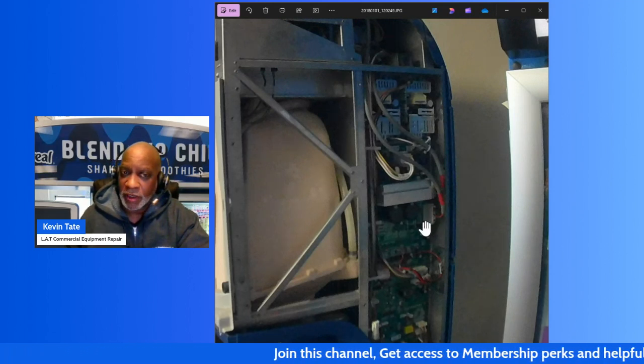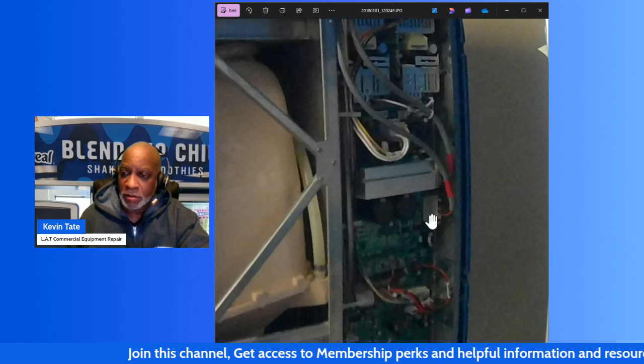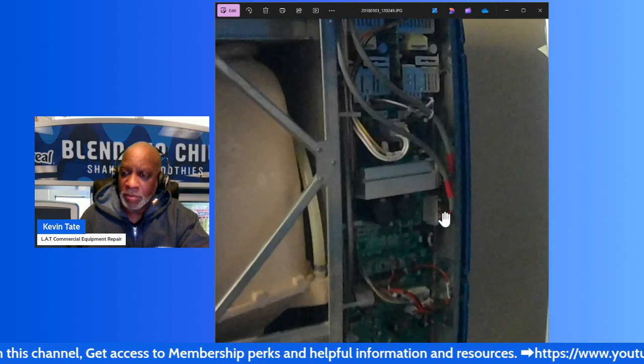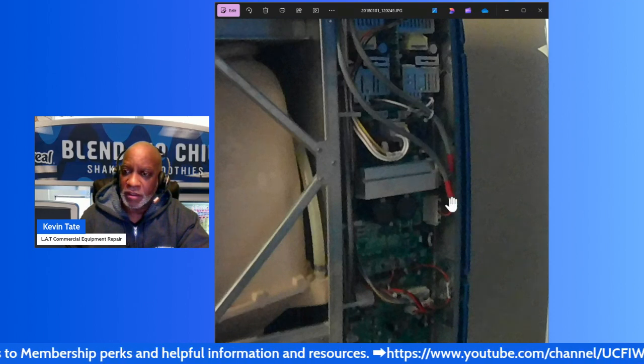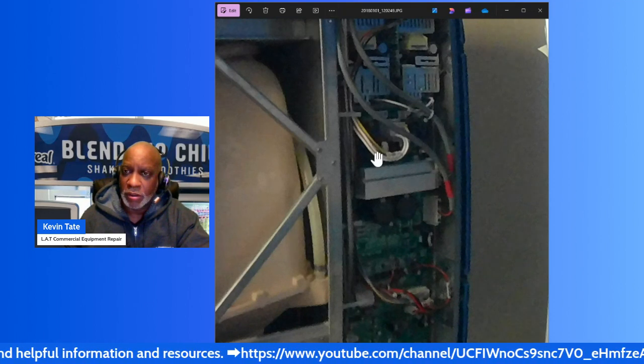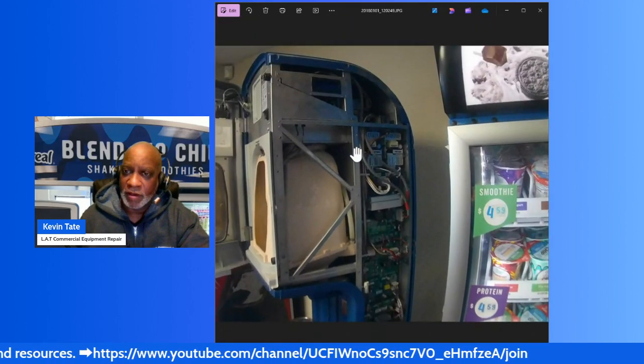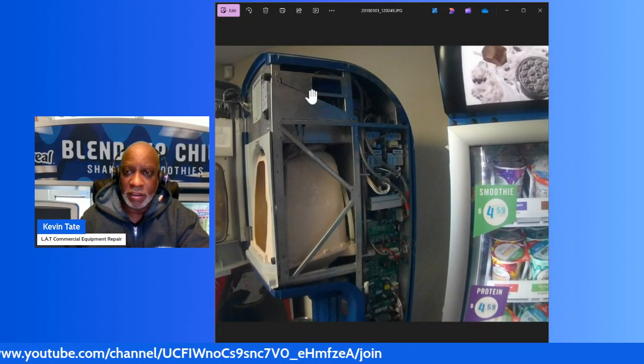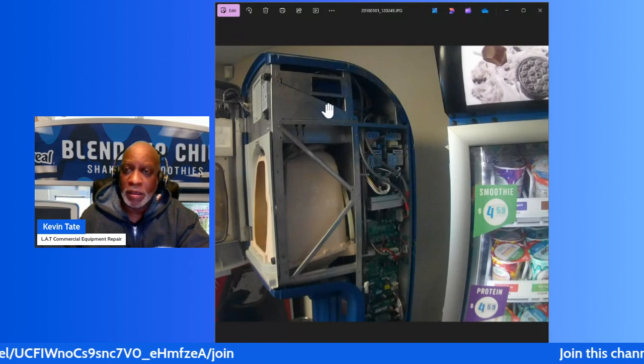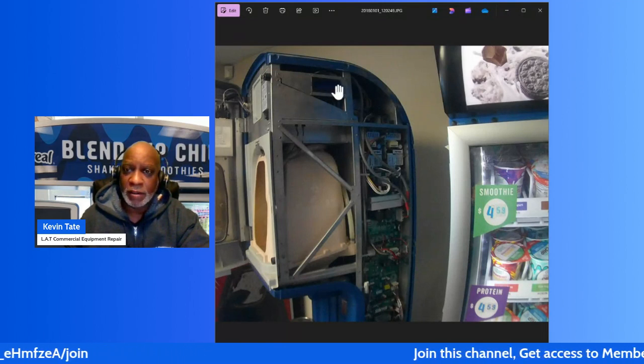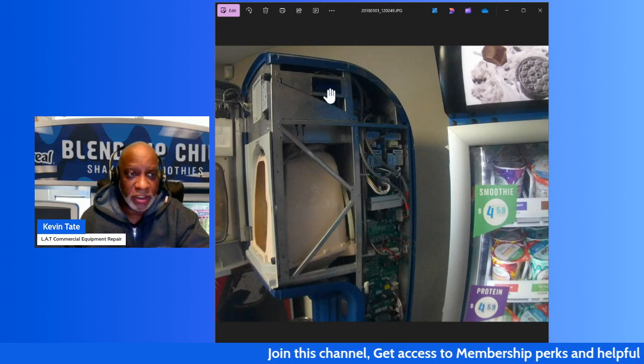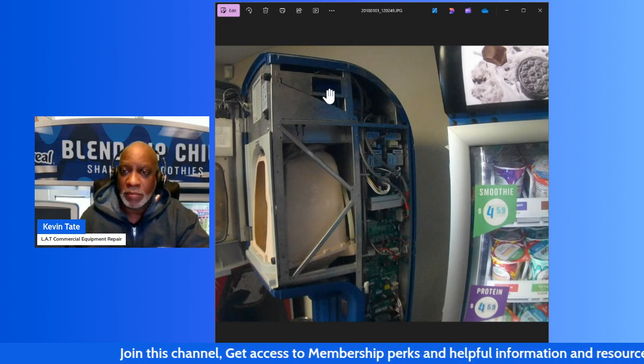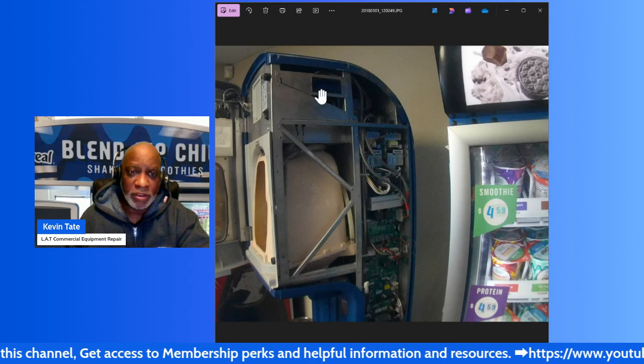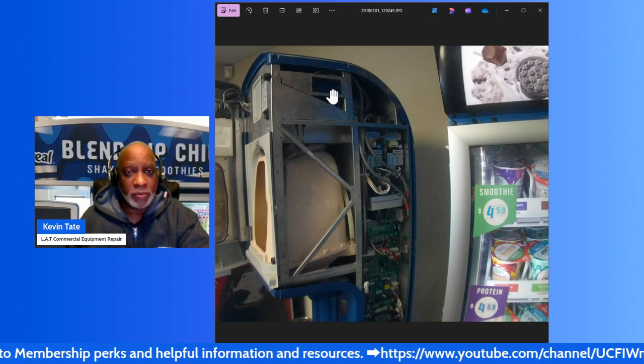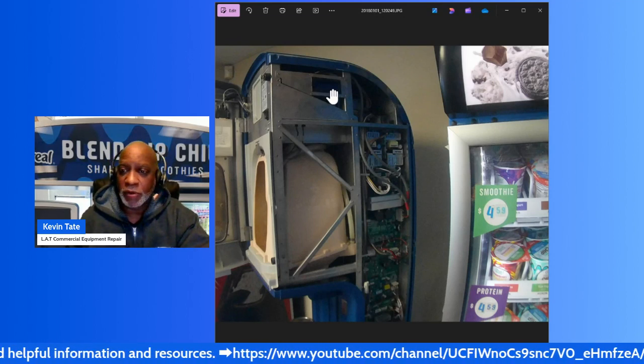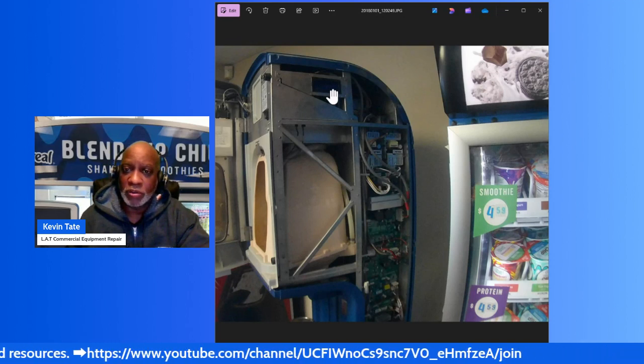This terminal right here, this white terminal, is the mix motor terminal, and that line goes up to the mix motor. The mix motor is on top, in the top section of the machine. This black screen is the display screen for the blender, and that's where the error codes and messages come up for you to diagnose the unit.